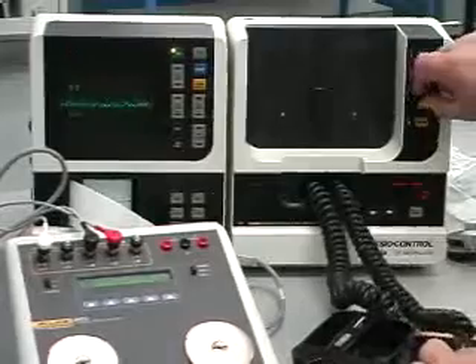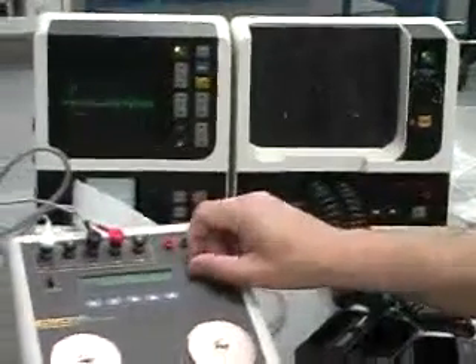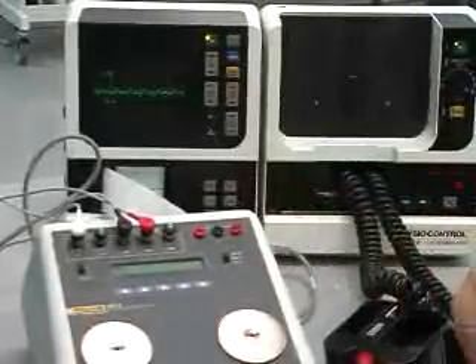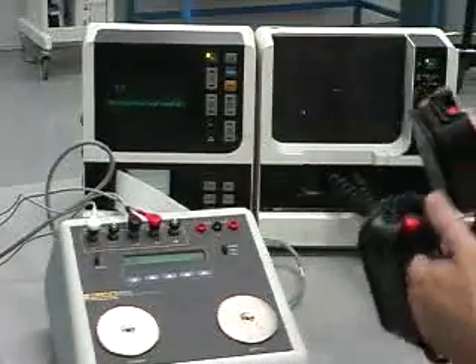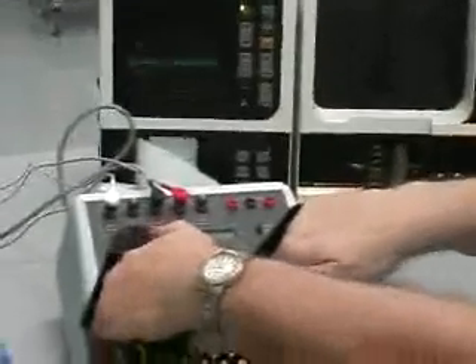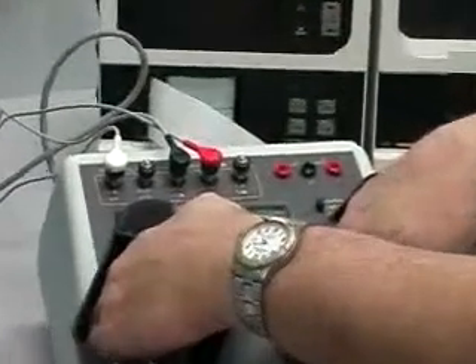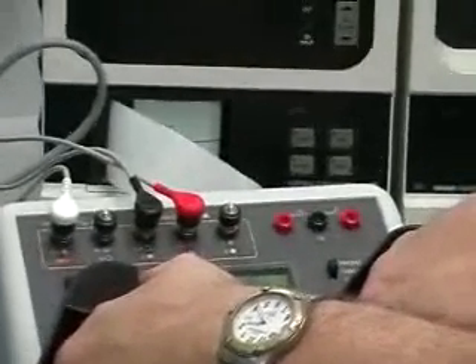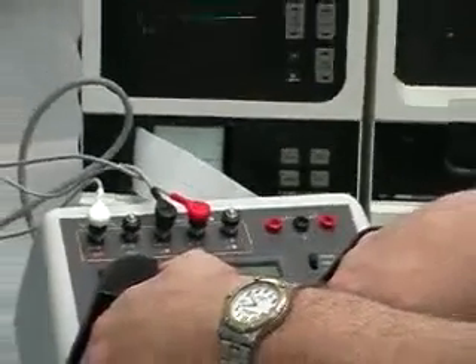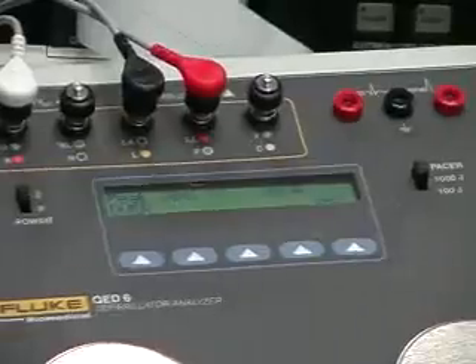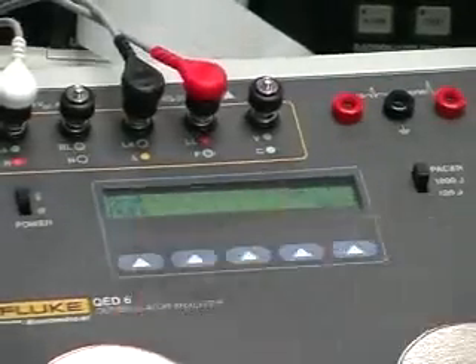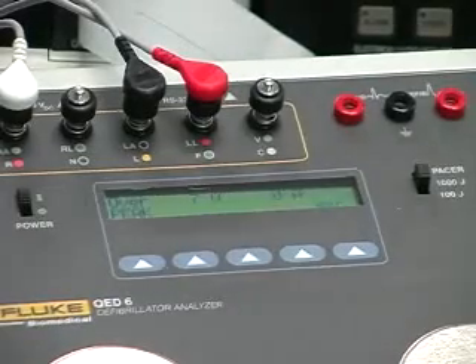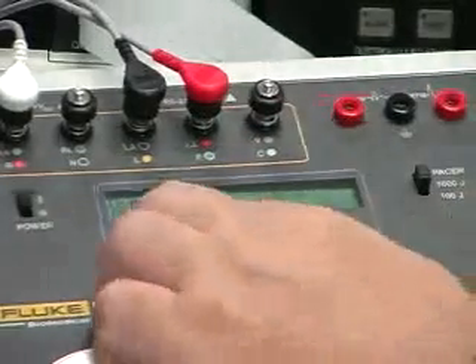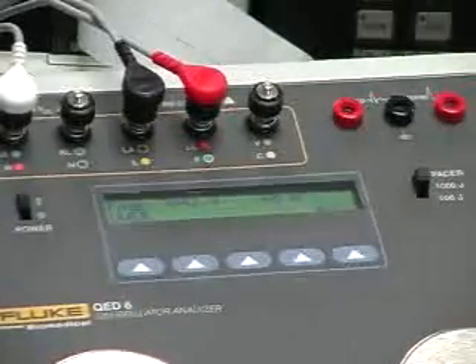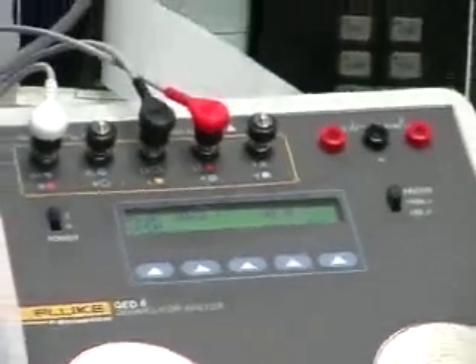Okay, so just to prove the point, we'll go up to the full energy capabilities. We're going for a full 360 joule discharge. And there we go, 60 amps right on the button. That's 60 amps through a 50 ohm load. And very little overshoot, only 7 volts. That's 7 volts out of 3,000, so very minor overvoltage.